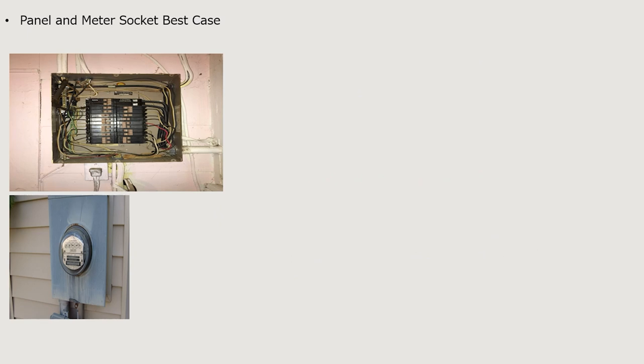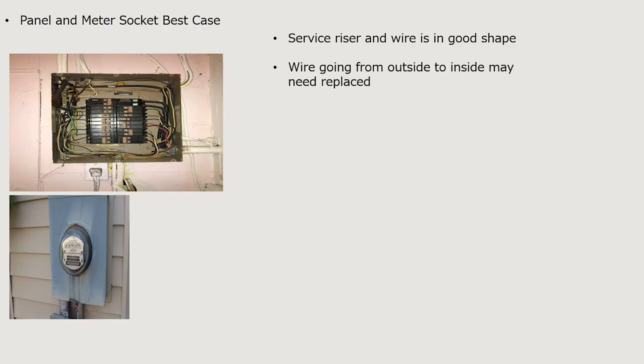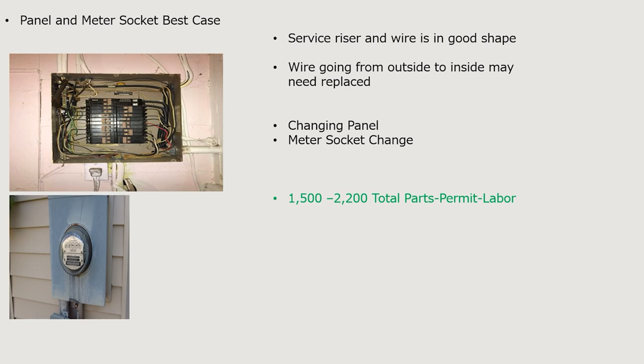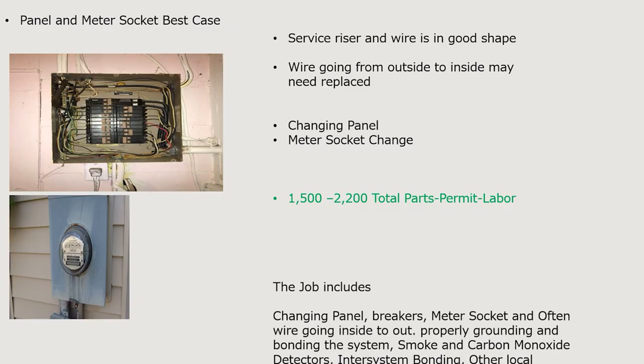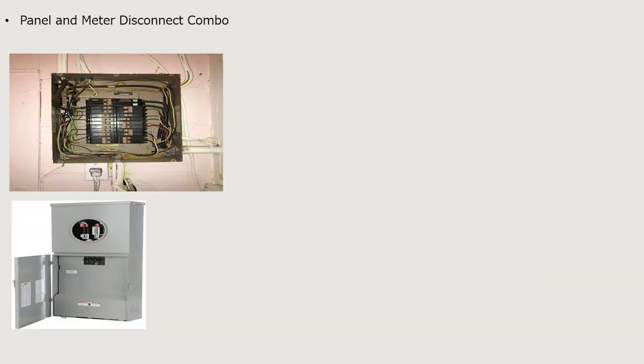Scenario two: panel and meter base — best-case scenario. We're coming out and changing the meter socket, assuming the service riser and wire are in good shape. The wire going from inside to outside may need to be replaced, and often it does. This inside-outside job is going to be between $1,500 and $2,200 total — parts, permit, and labor. It often can be done in one day but adds quite a bit of labor, as it can be logistically tough to change out the meter socket.